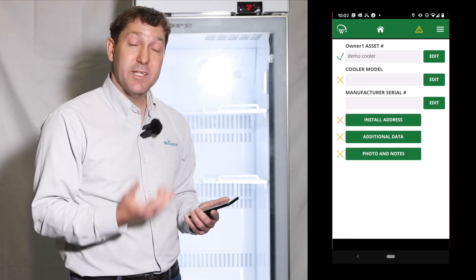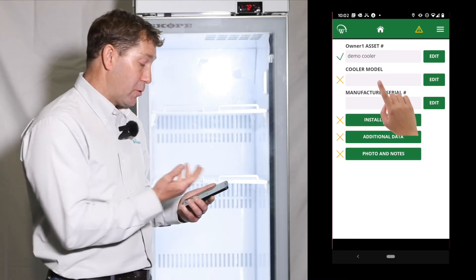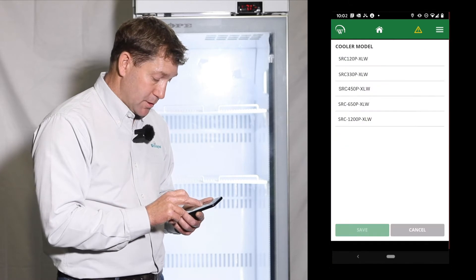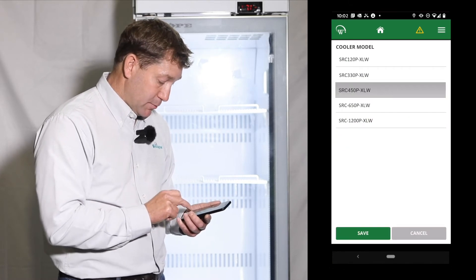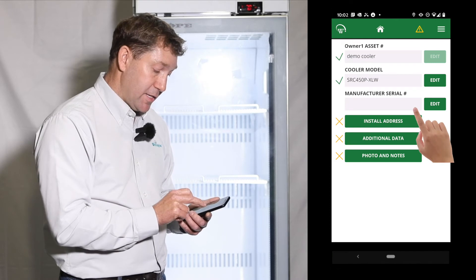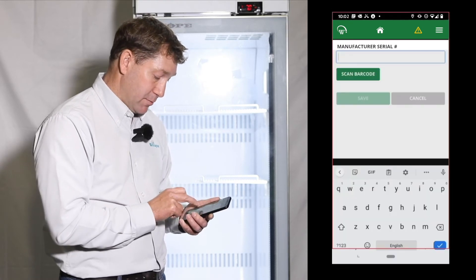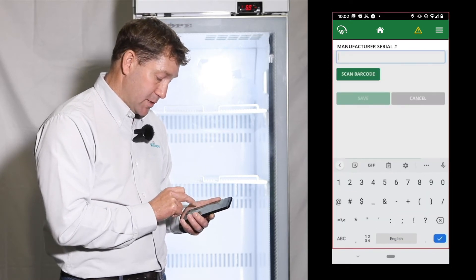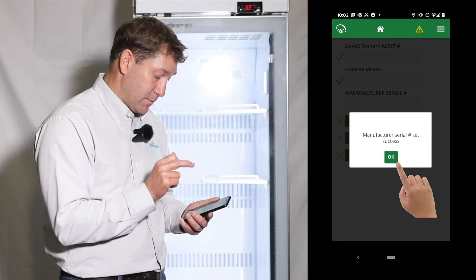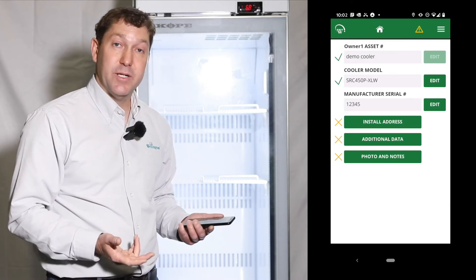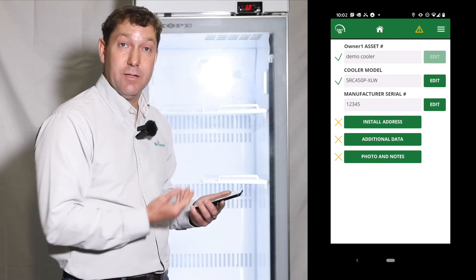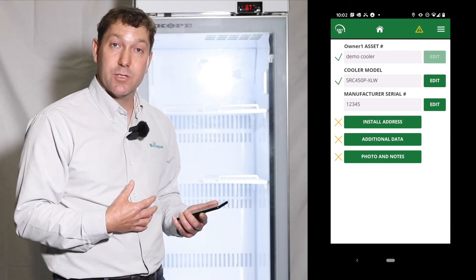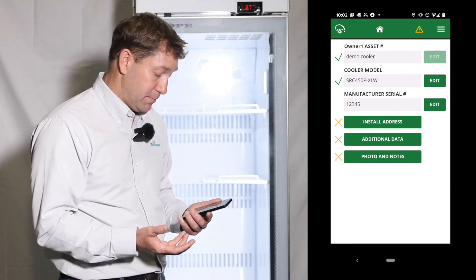We can then add additional information if we require, such as the model, so I can edit here, select the model, and then a manufacturer serial number, which maybe is 12345. This information is now saved inside the monitor and anybody who comes along will see the monitor in future.